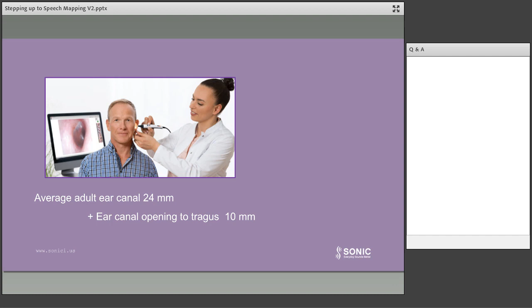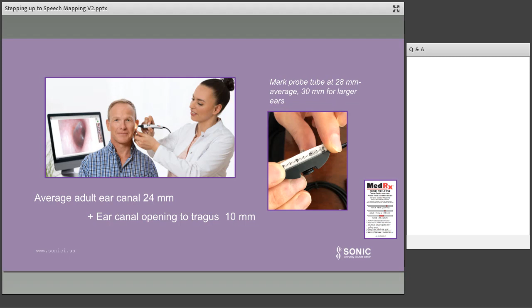If you're not deep enough, then what's going to happen is when you start to run your test, you'll see that there's not enough gain in the high frequencies, around 3 or 4K, that you'll be pushing up the gain handles and nothing's happening. So my recommendation is always, when you start your test, if your high frequencies are not quite up high enough, the first thing you should do is move that probe tube in another couple of millimeters. And you know what? Many times that just moves the end of that probe tube out of the dead zone for that frequency, and all of a sudden those high frequency levels pop up again. So that's a very important thing to consider when you're doing speech mapping.